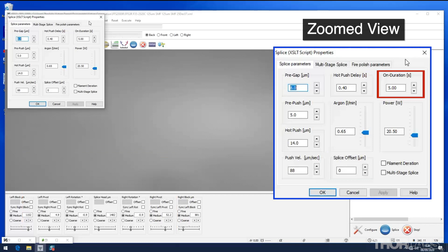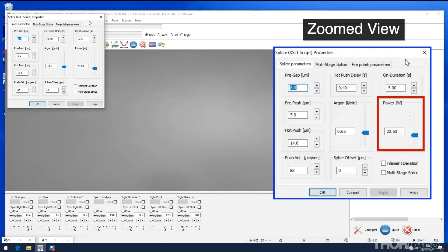On duration is the time in seconds the filament stays on after the hot push delay time. Power is the nominal electrical power of the filament. Because the thermal response of the filament changes over its life, a filament power offset that is determined and set by the normalization procedure is added to this nominal value by the software.